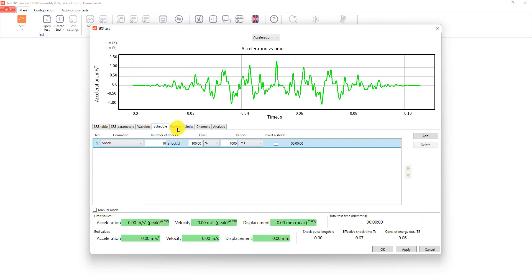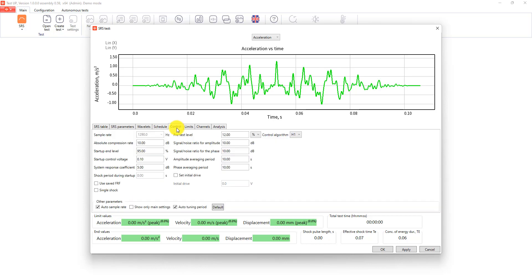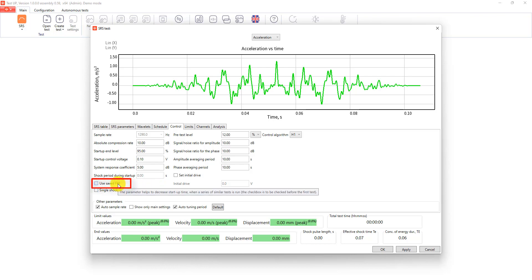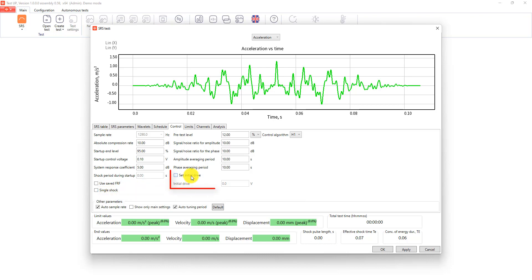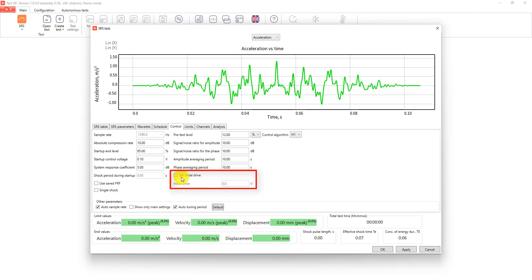In the control tab we will leave the main settings by default, but I will explain some additional features. Use saved FRF option can be used to improve the startup speed of your test if you are running the series of identical tests using the same equipment. Single shock option increases the startup time, but in this case the system won't do any shocks during the startup. Also you can set the initial drive value which will be used during the startup, but you should know this value and be really careful with this parameter.